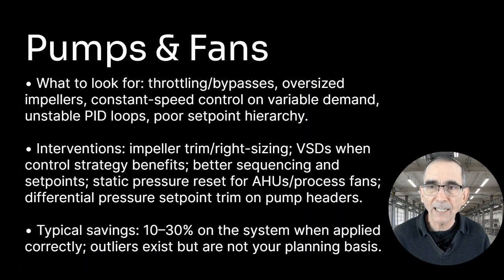If you're looking at pumps and fans or motor powered items, there are many things to look for, such as throttling or bypassing. Is it operating at the correct point of the duty curve? Are the impellers oversized? How's the speed controlled? Is the control loop stable? Some possible interventions would be impeller trimming, or putting on a VSD and slowing it down a bit, or a control strategy where your speed varies through a variable speed drive, variable frequency drive, VFD. Maybe better sequencing, better set points, maybe some pressure sensor-based control to modulate speed, such as on air handling units or on pumps. The typical savings could be 10 to 30% on a system when applied correctly. Outliers exist, but that's a typical range.